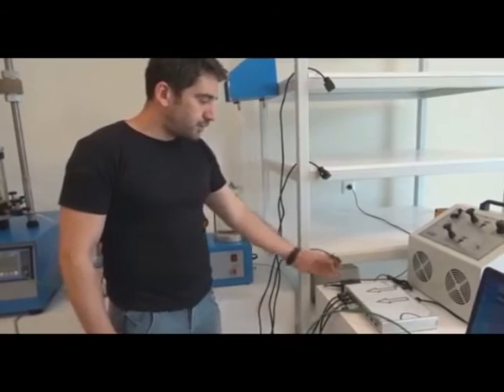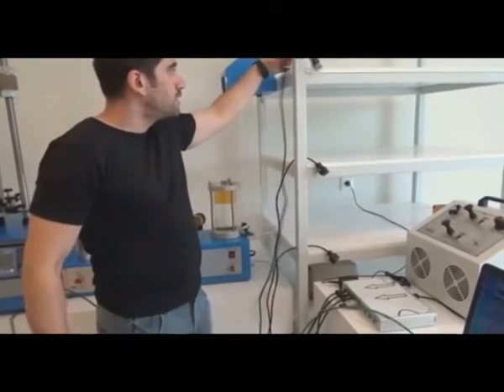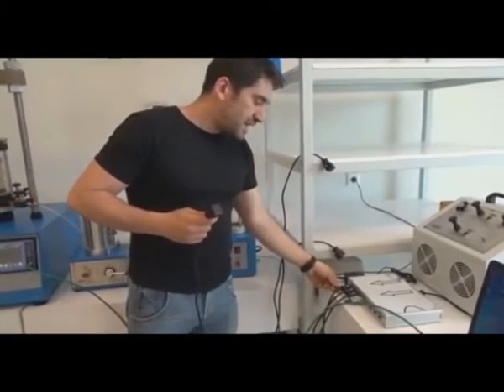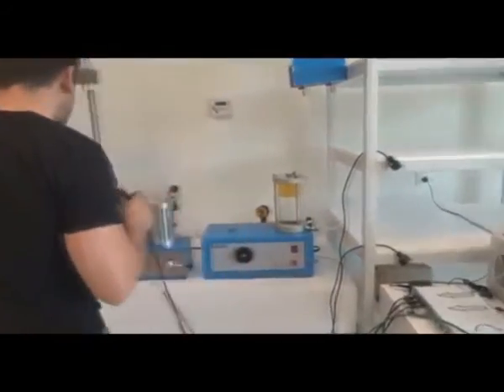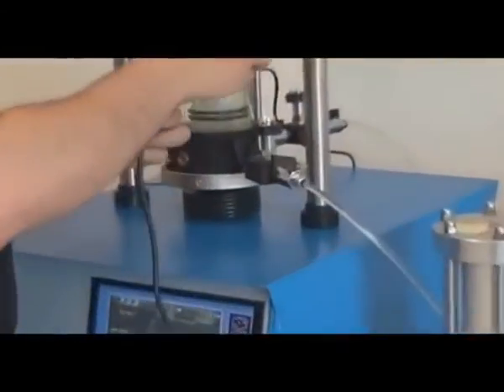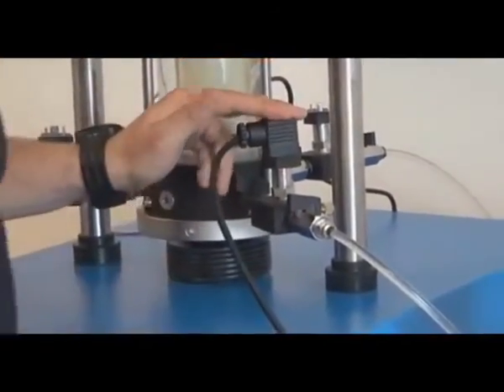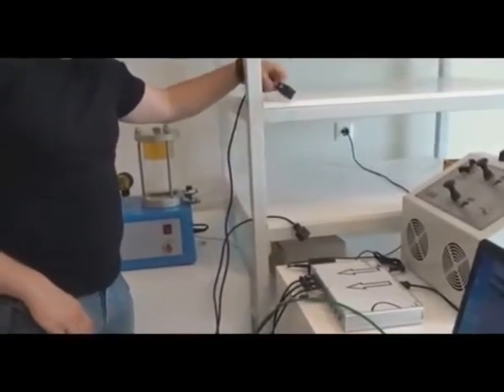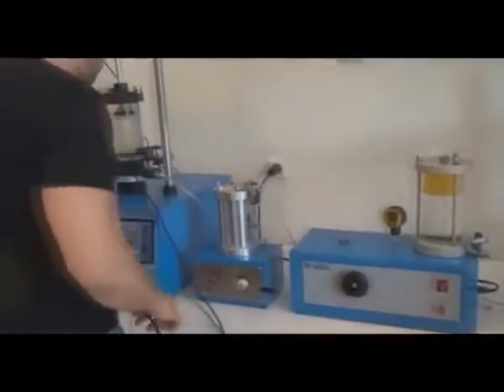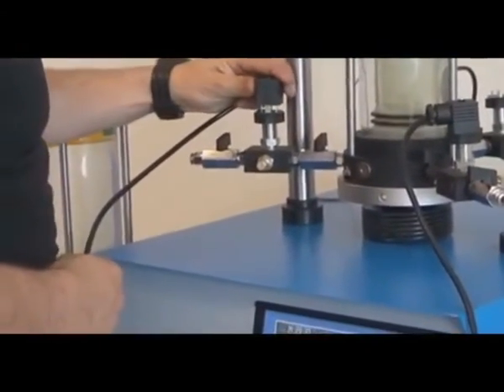We have up to 4 different specimen types here. Since we are working with the first specimen, we are choosing specimen number A. Current test stage and previous test stages are 0 because we haven't started the test yet. Now we are going to connect the data logger to the pressure transducers using these connection cables. The first channel is for cell pressure, so it is connected to the cell pressure transducer. The second channel is for pore pressure measurement, so the second cable is connected to the pore pressure transducer.